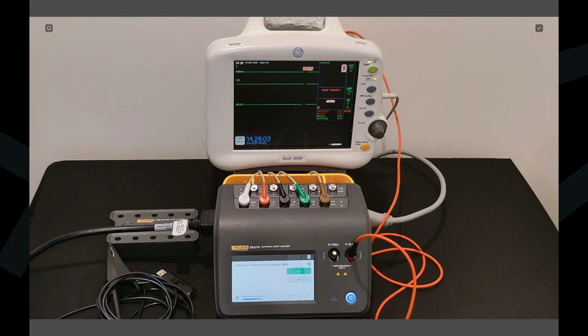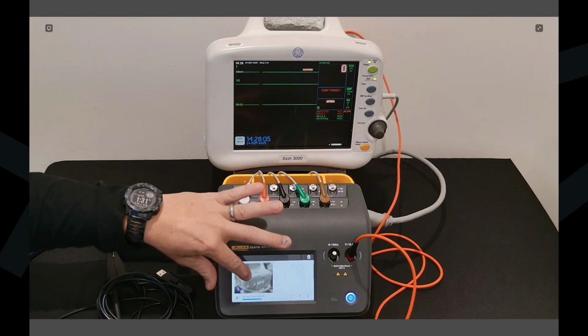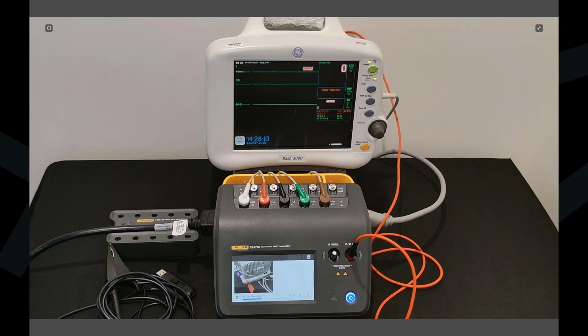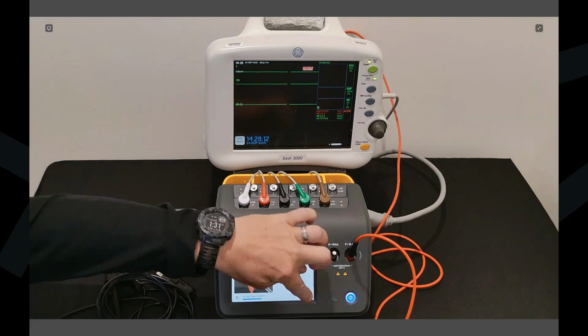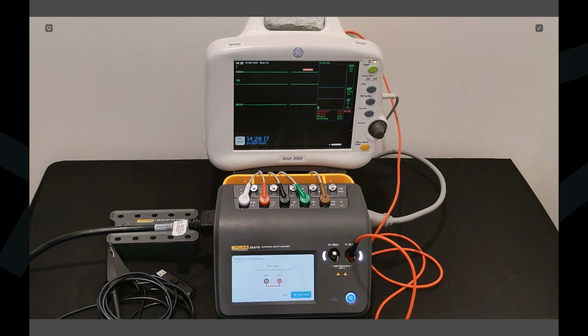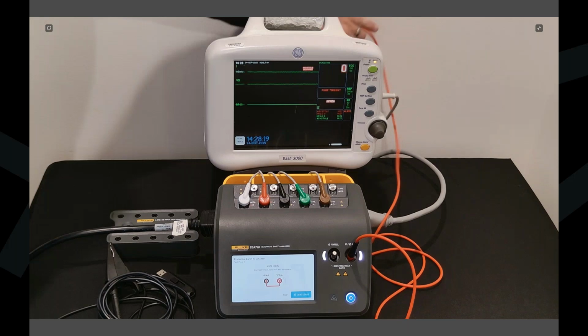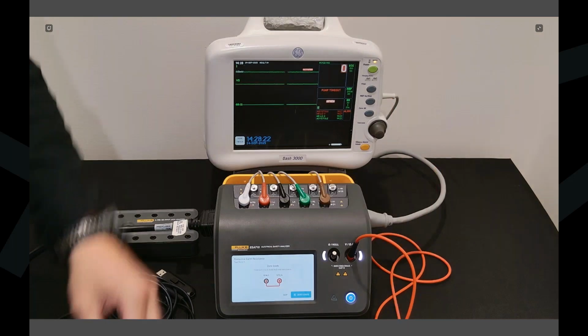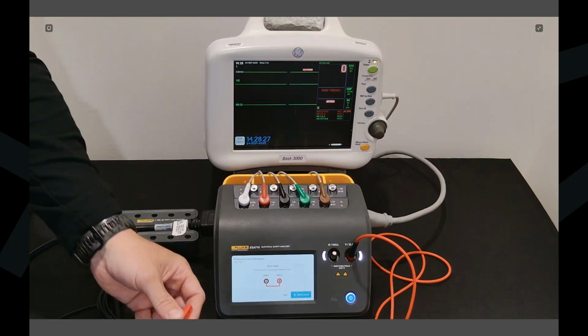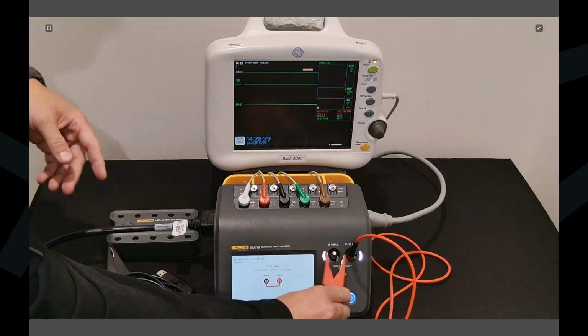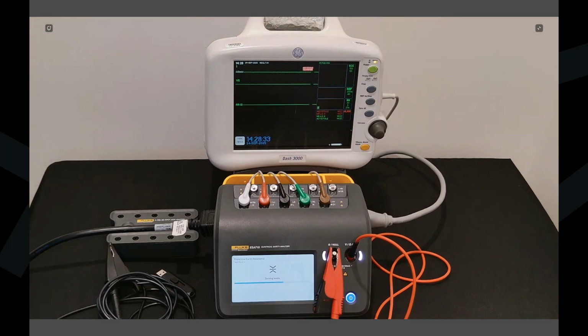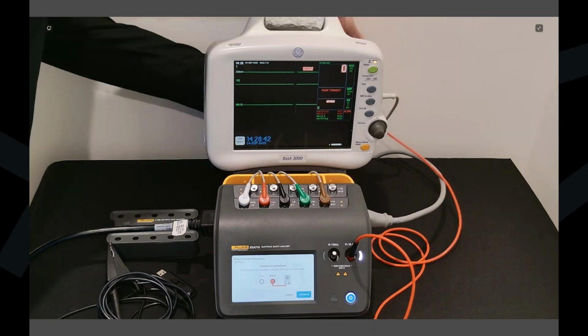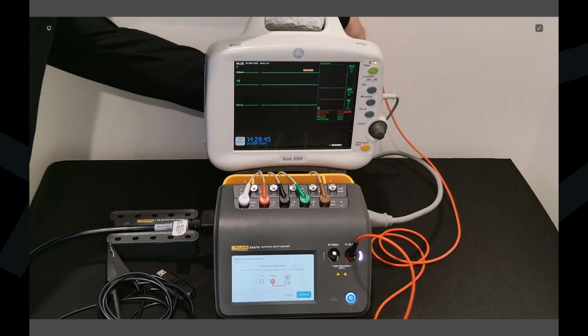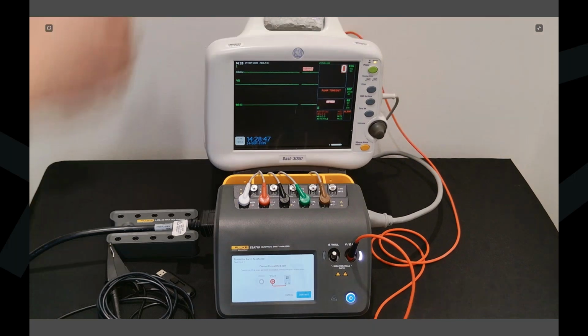So here again, another picture illustrating where do you hook up your protective earth. But before we do that, it's going to ask me, you need to zero your lead. So typically you zero your lead every day. Again, letting you know, this is where we zero lead, LED indication. Just doesn't get much easier than that. So you zero your lead. And now we're ready to connect to our protective earth. Now we'll start our electrical safety testing.